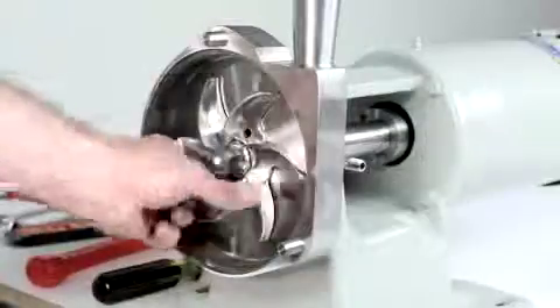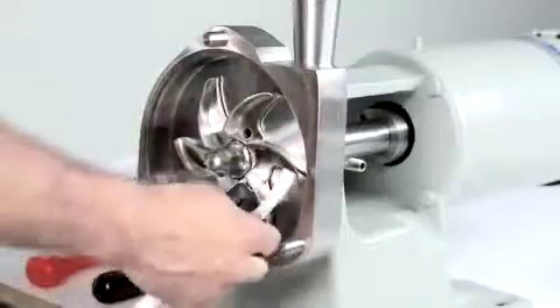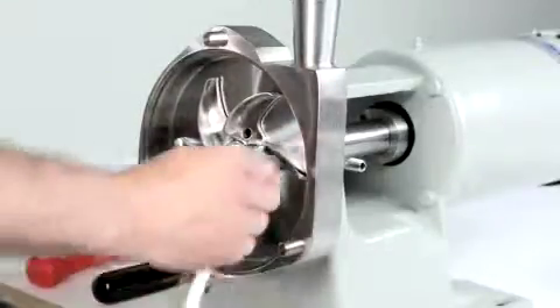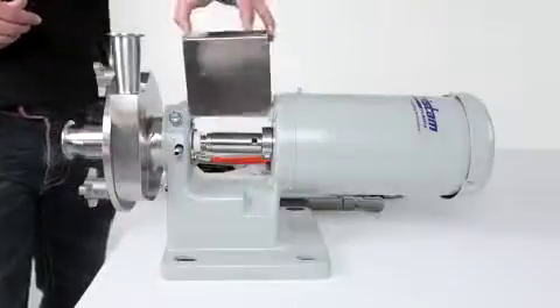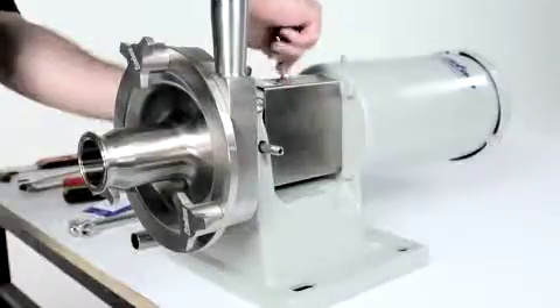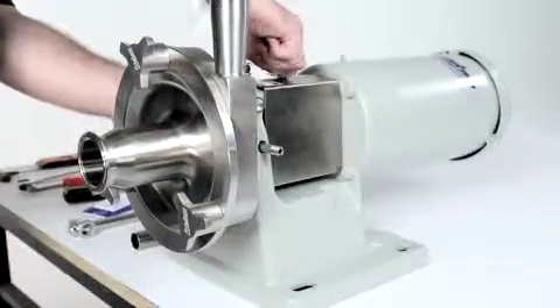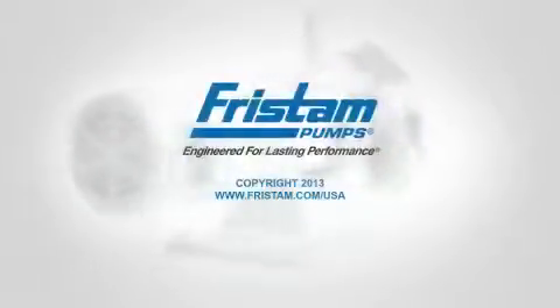Remove the feeler gauge. Check the gap on each blade of the impeller to see if the gap on each blade is correct. Reinstall the cover and flange guard as previously shown. The pump is now ready to be placed back into service.